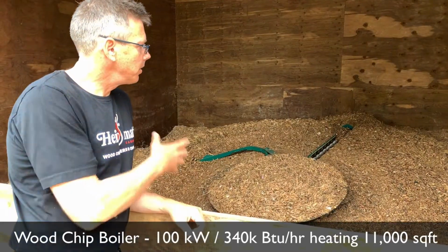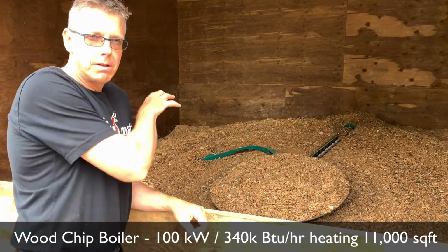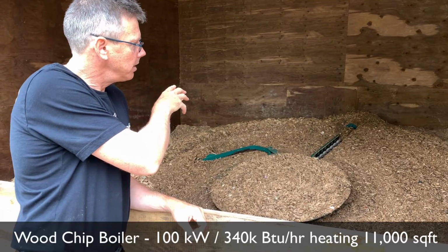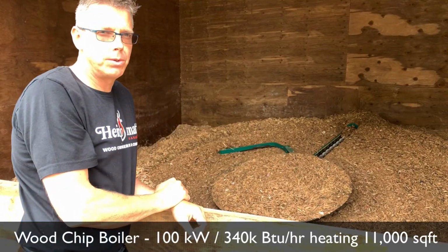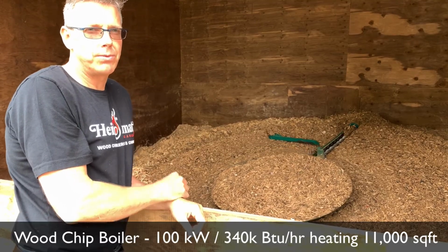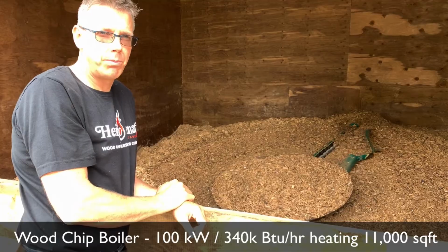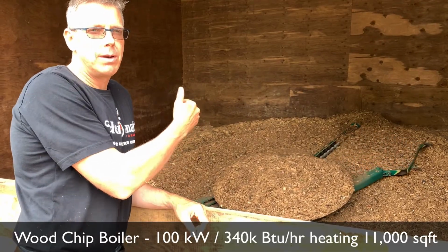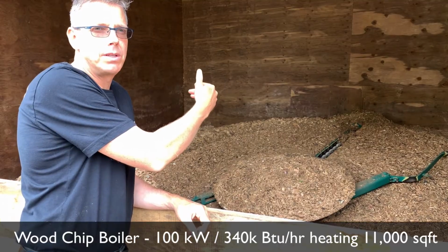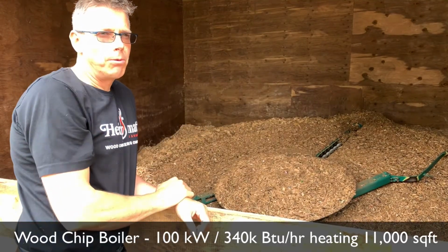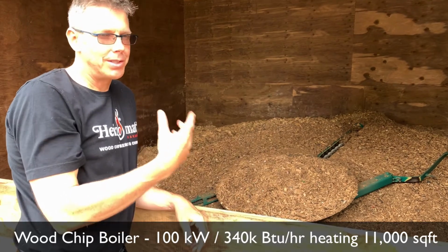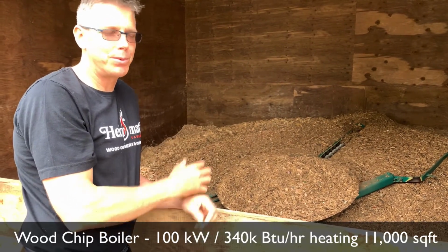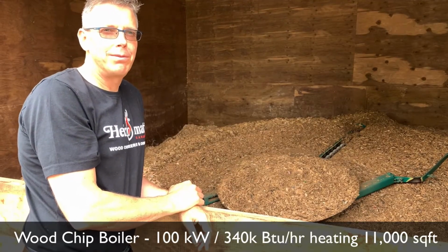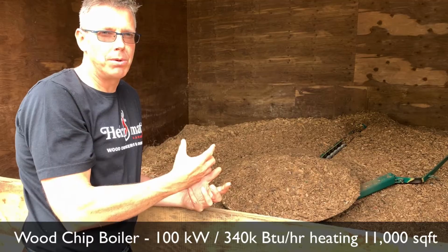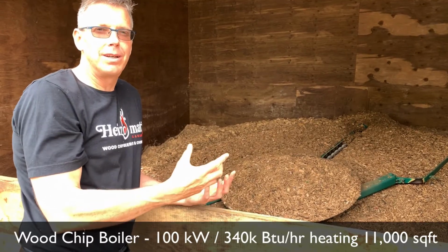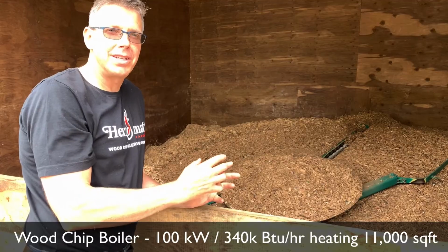There are also a lot of refinements that are hard to see from here. On the auger, the flighting is larger as it goes into the closed auger system than the smaller flight in the open auger, because it needs to move more fuel, so we never get jamming as fuel passes from the open auger into the closed auger. Wood chip isn't like pellets — pellets flow nicely, you can move them through a vacuum system or a funnel. Chips vary a lot in size and can cause jamming and all sorts of problems. If you try to feed wood chips through a round auger in a round casing, you'll always get jamming.